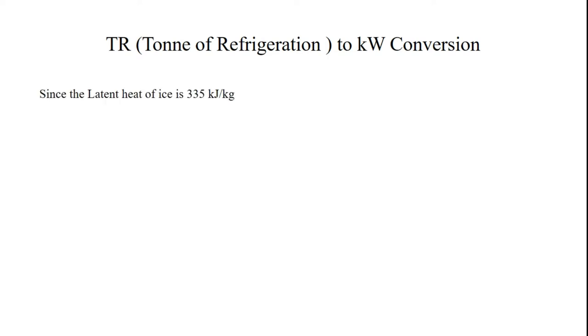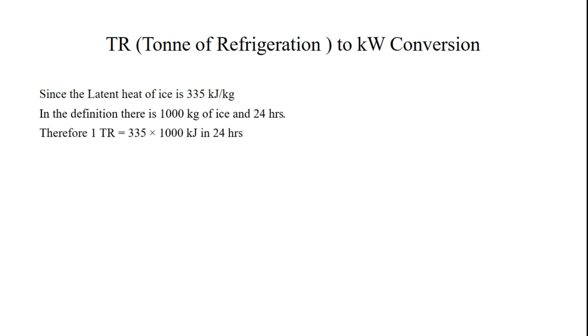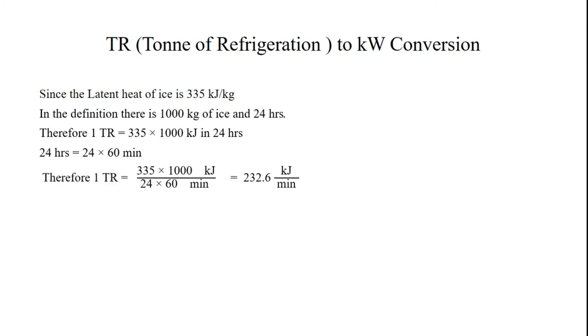Now let's see the conversion of TR to kilowatt. Since the latent heat of ice is 335 kJ/kg — latent heat being the amount of heat required to cause a phase change — and the definition involves 1000 kg of ice over 24 hours, 1 TR equals 335 × 1000 kJ in 24 hours. Since 24 hours equals 24 × 60 minutes, 1 TR equals 335 × 1000 divided by (24 × 60), giving units of kJ per minute.